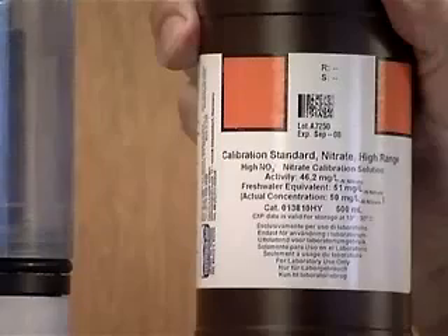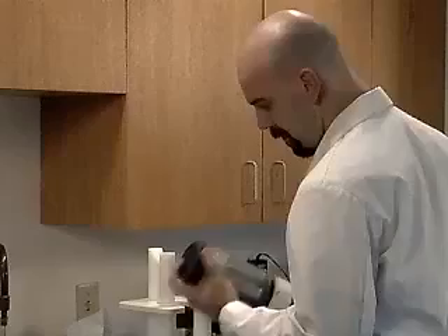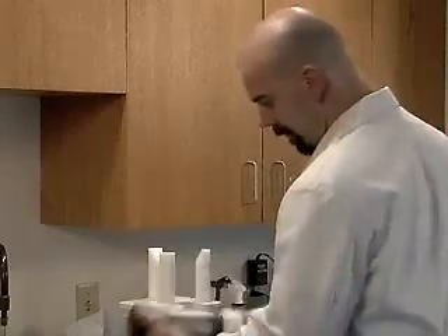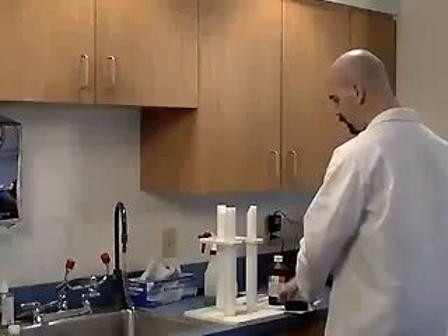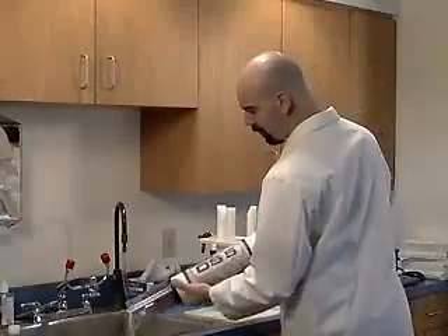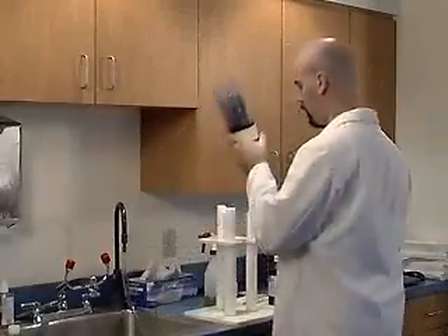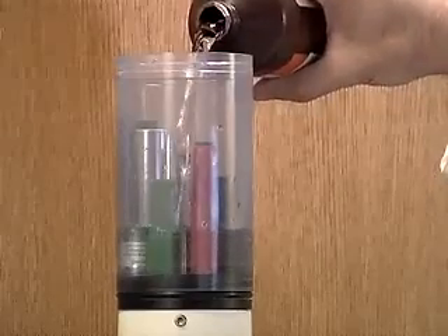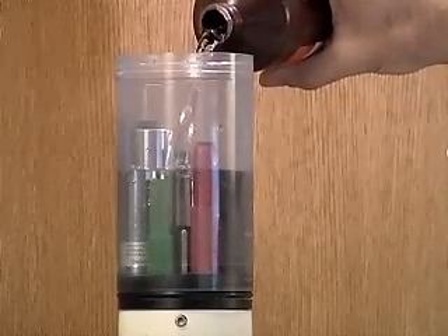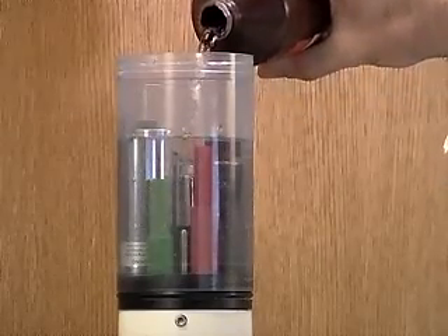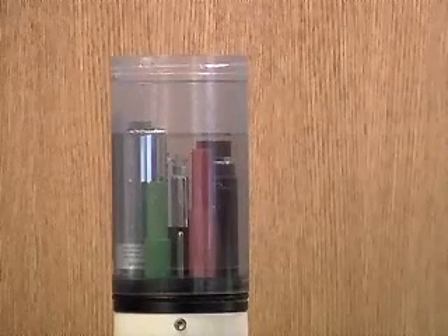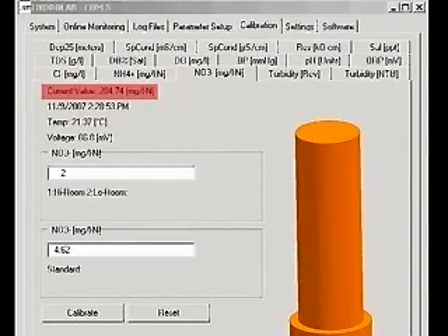Fill the cup about 25% with the room temperature high standard and screw the storage cap on. Shake for 6 seconds. Remove the storage cap and pour the standard out. Fill the cup with room temperature high standard again, this time covering the ion tip and the pH sensor. Wait 5 minutes for the readings to stabilize.